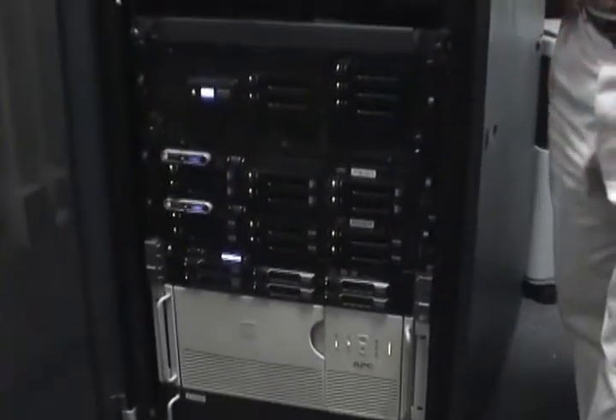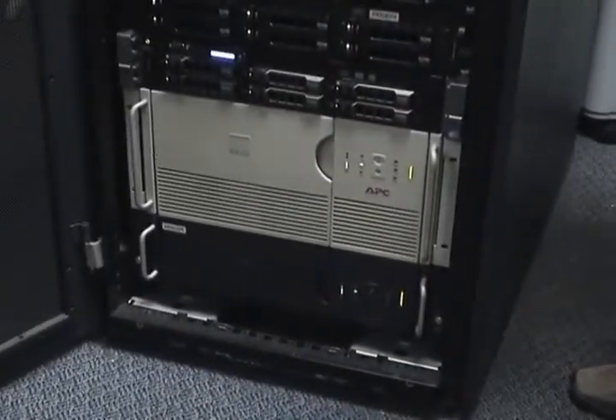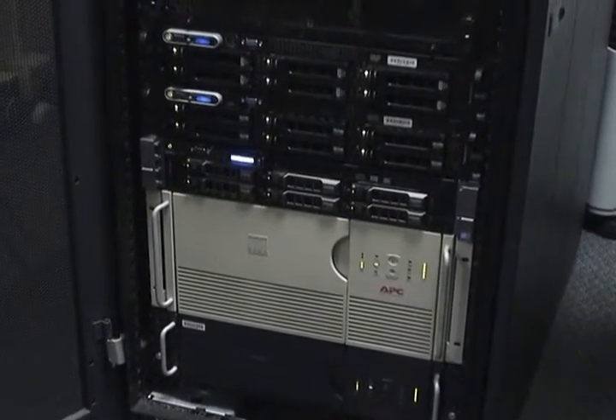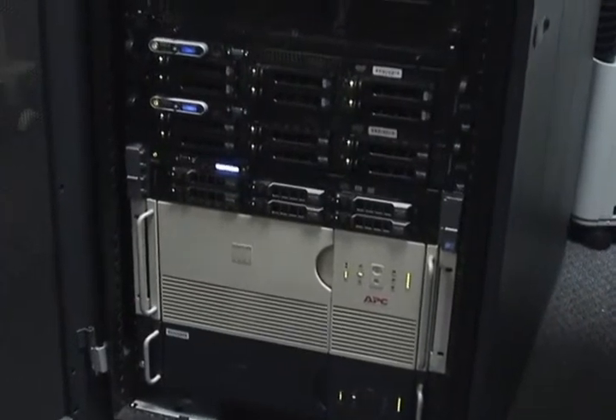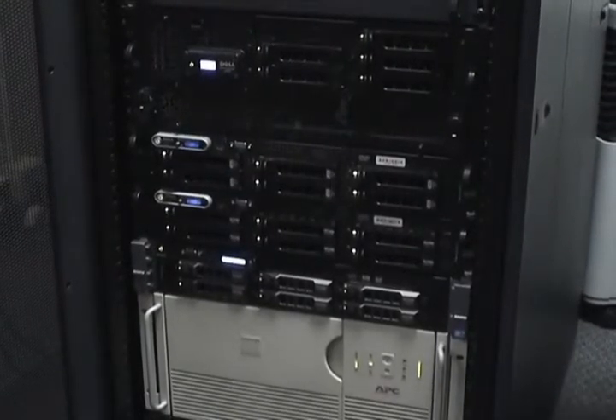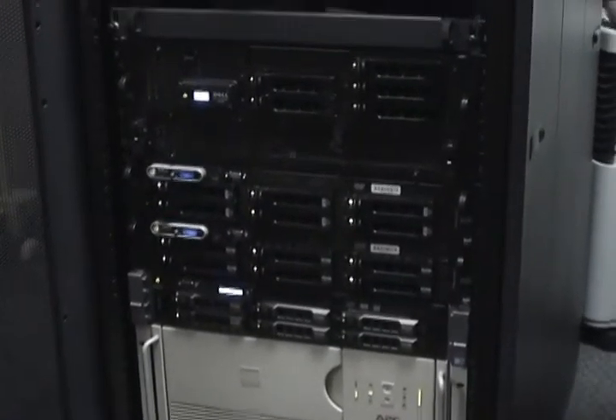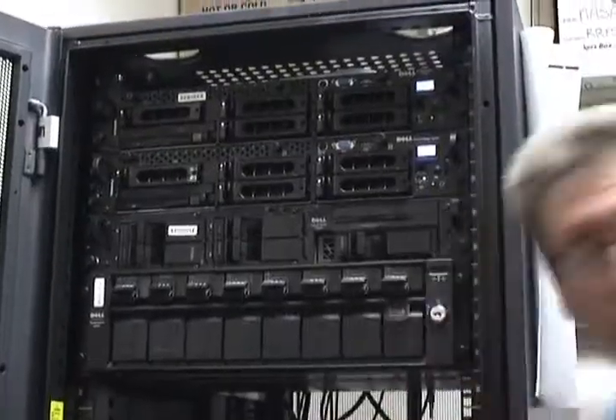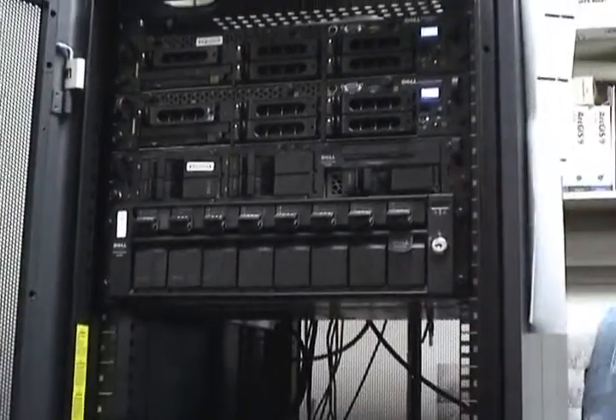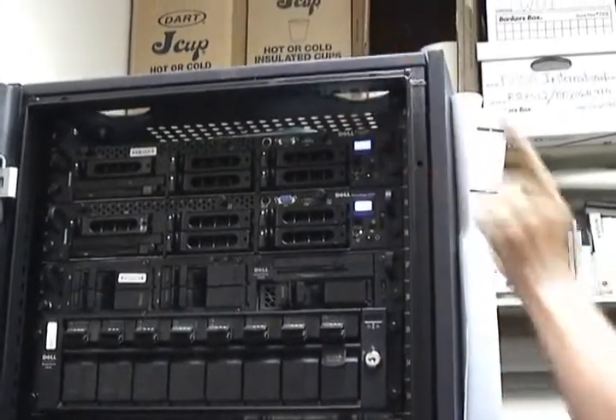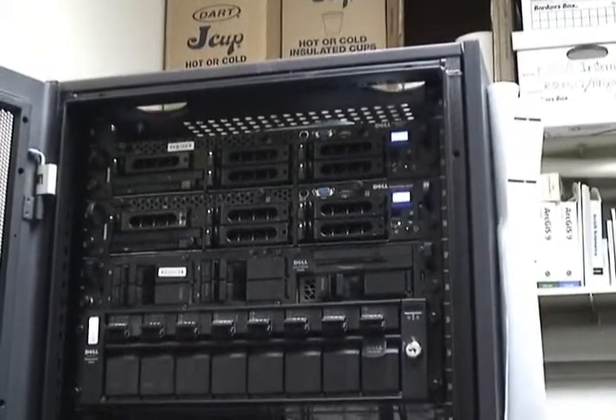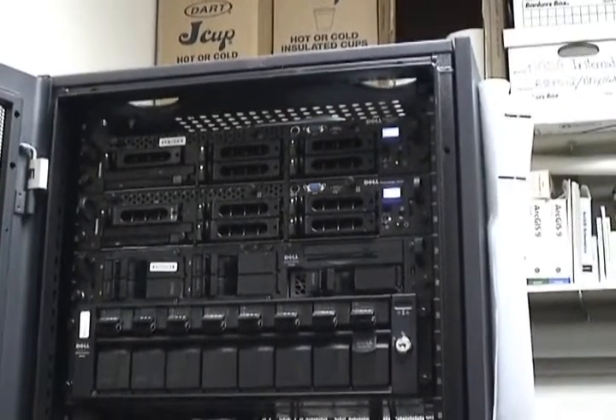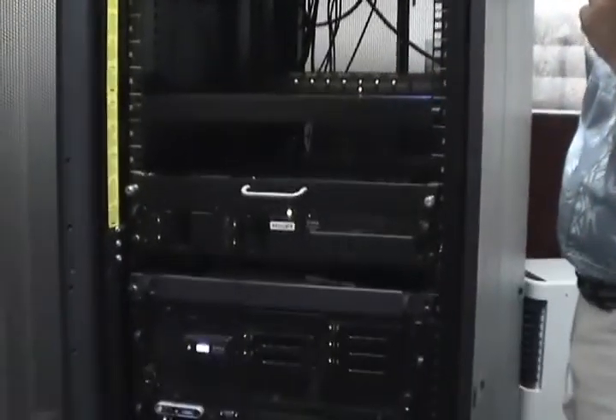So one is feeding this UPS, the other feeds that one. Now each of these servers here has redundant power supplies. In fact, they're hot swappable also. So if one goes out, they're both sufficient to run the server. And if one goes out, we can leave the machine running, pull out that power supply, pop in a new one, very modular type of design, and we're back up and running. So for this machine right here, one power supply is plugged into this backup power supply, the other one's plugged into that one. The only way to bring down any one of these individual servers is for both of those electrical lines to get cut or shut down. Essentially it means the whole campus has got to be completely out of power and probably most of Pocatello before these servers come down. So that's pretty cool. We've got a real nice robust system electronically that way.